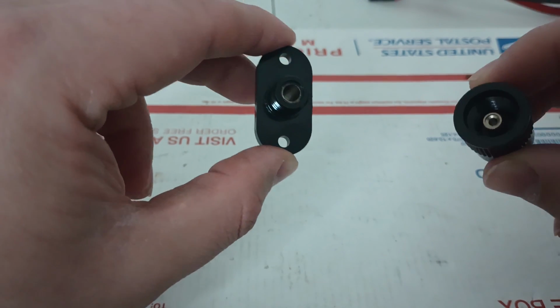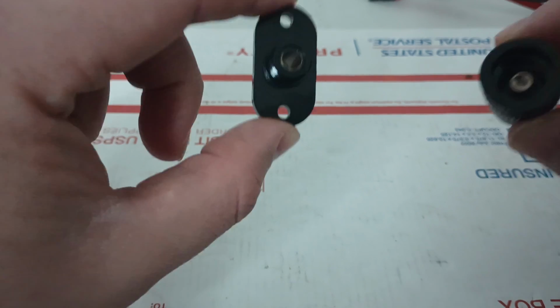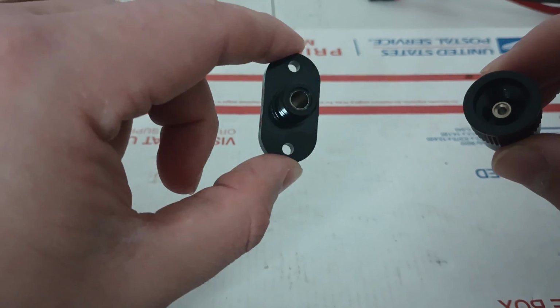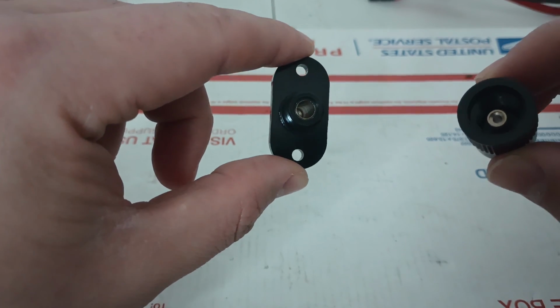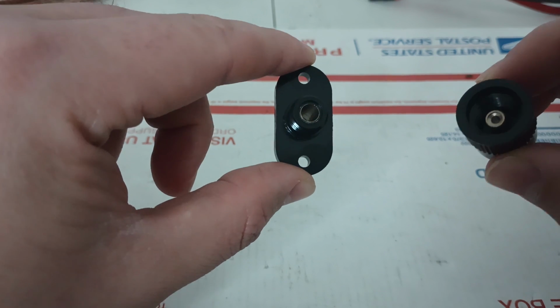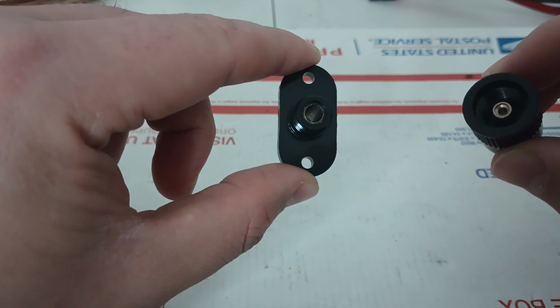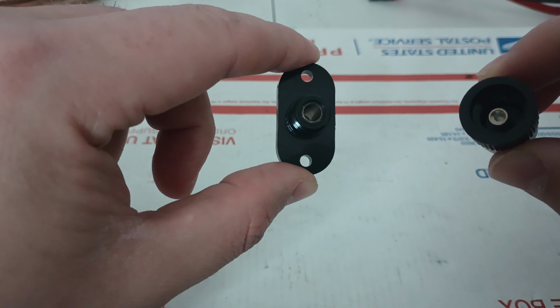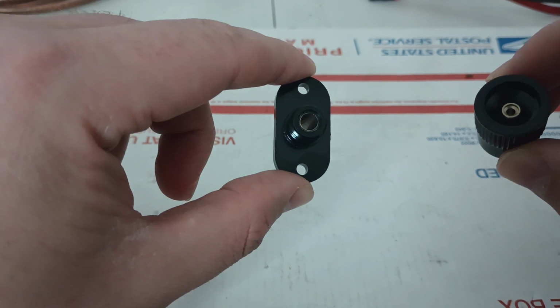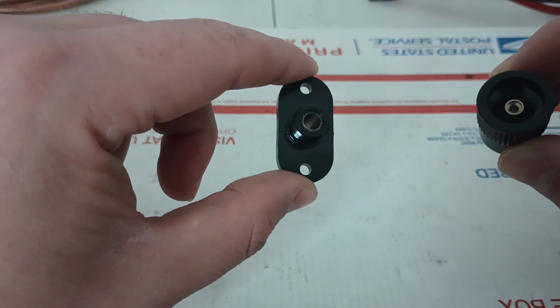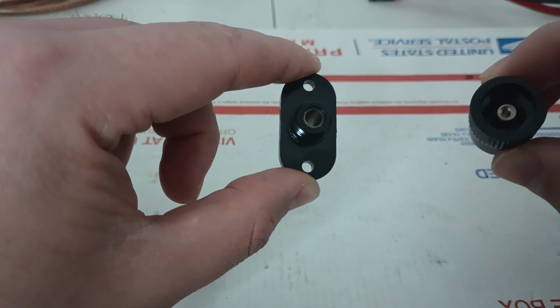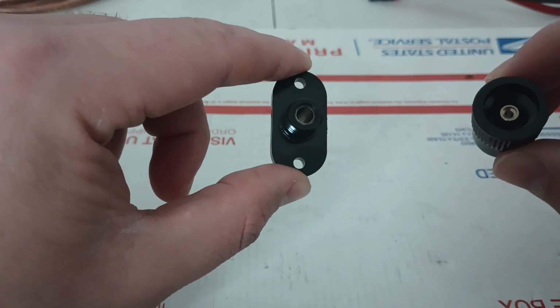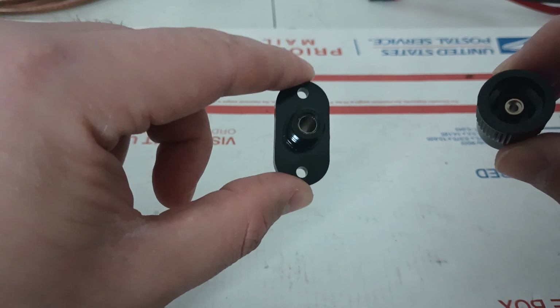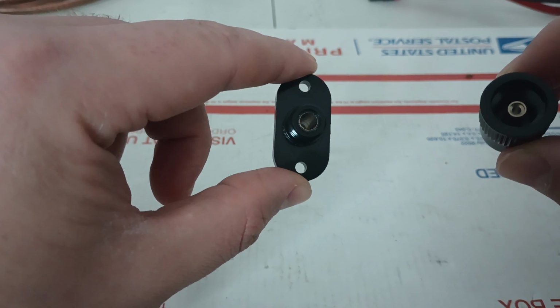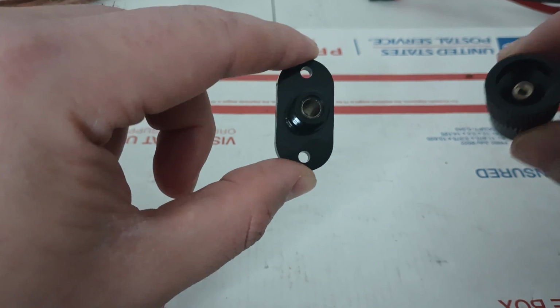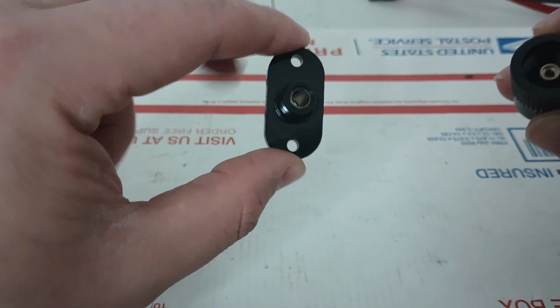Do not let someone build you an amplifier running an excessive amount of voltage through these connectors. If it's over 5,000 volts, give or take, you've got a little wiggle room, but I would not run these to the max voltage. Just because they're rated at 6,000 or 6,500 doesn't mean you need to run them at their very max rating.